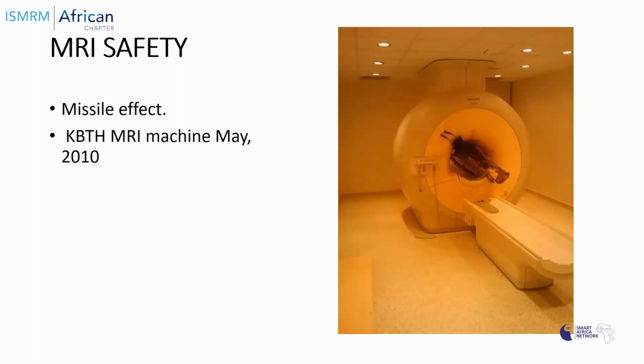Our hospital, Korle Bu Teaching Hospital, also had an unfortunate incident in 2010, whereby a patient, unknown to the staff, got to the entrance of the MR machine room whilst wheeling the father in a wheelchair which is not compatible. Before the staff could realize, there was this missile effect, and the wheelchair was thrown into the MR bore. The son was able to hold on to the father, so he was not hurt, but the wheelchair was thrown into our MR machine, and they later had to call experts to come and quench the machine before the wheelchair was removed. This was rather unfortunate.